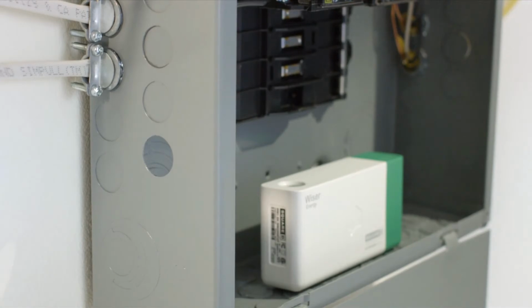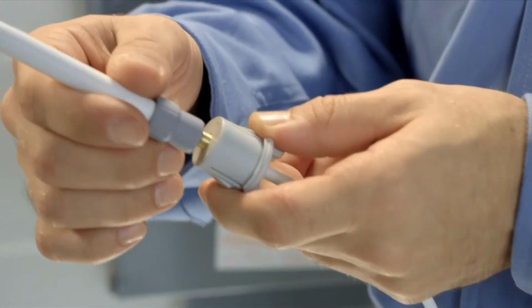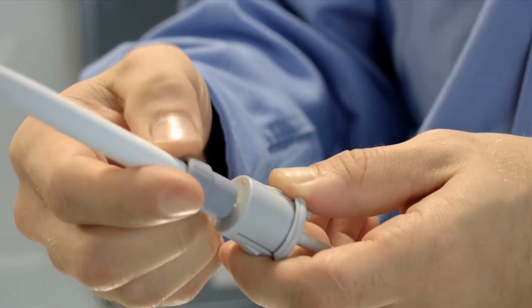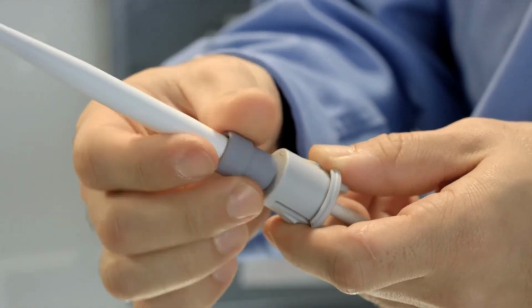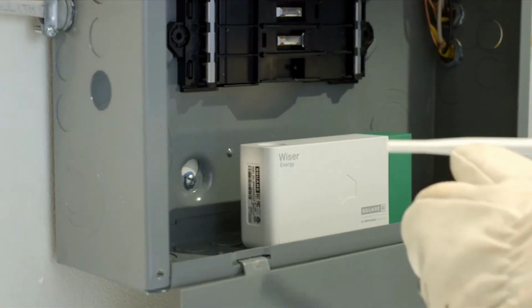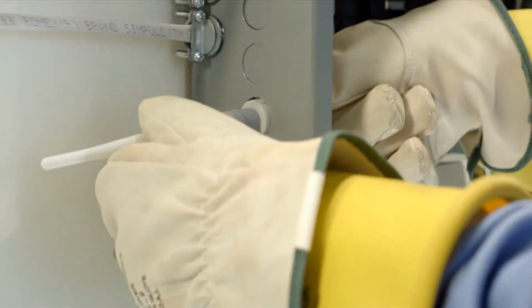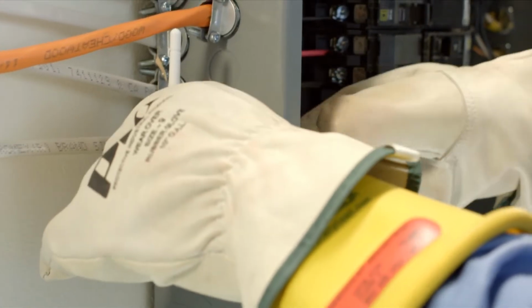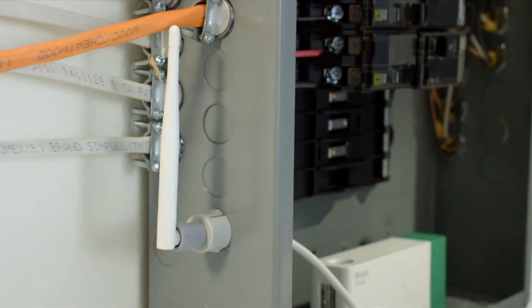You'll first have to remove a 1/2-inch knockout, as the antenna has to go on the outside of the electrical panel. Slide the antenna insert onto the antenna extension cable. Next, screw on the antenna. The antenna and the insert should then be pushed through the knockout. For flush mount panels, the antenna can still work within the wall. For outdoor panels, the antenna must be in a bottom knockout.